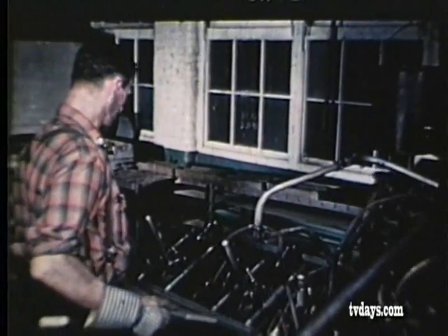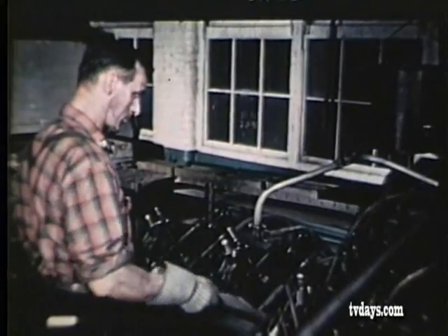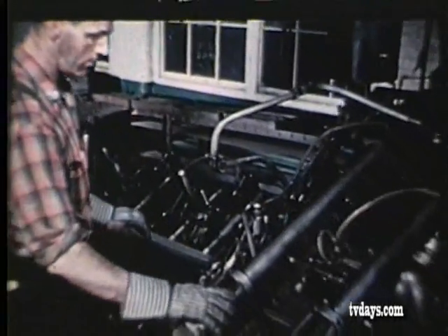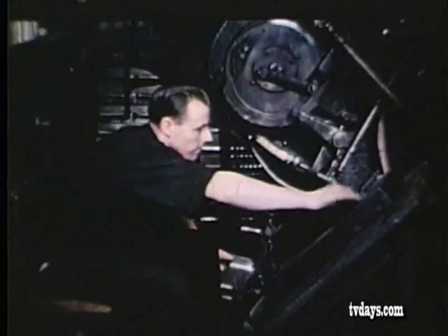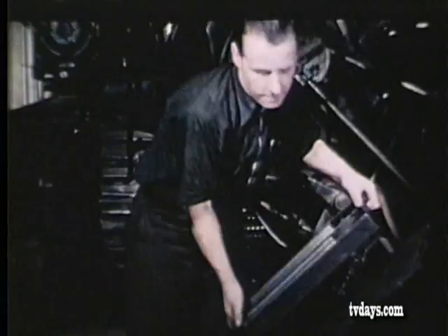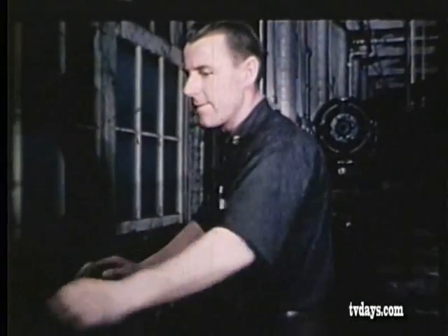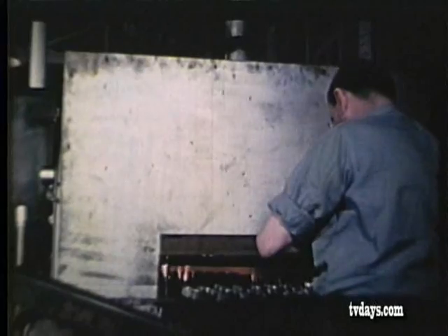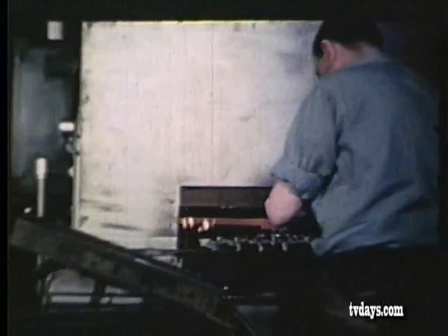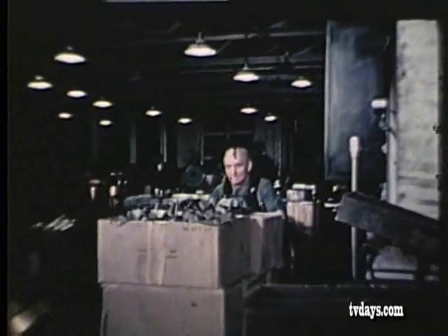In another building, we see strips of silicon steel being placed in an automatic punch press. Vacuum cups pick up each strip and slide it under the press. The waste is thrown out while the punchings themselves march out at the back, to be carefully placed in a box, started on their way to a General Electric controlled atmosphere annealing furnace for a heat treatment which assures uniform electrical characteristics. The curtain of flame prevents air from entering the annealing chamber.